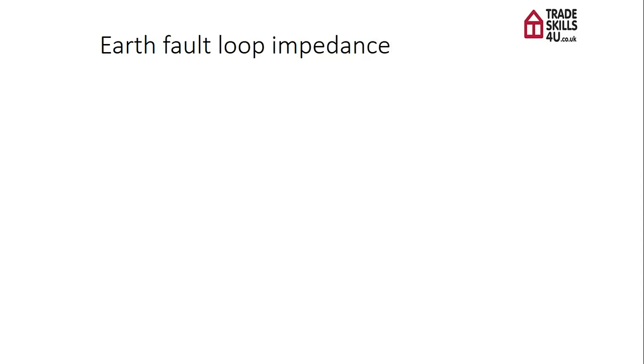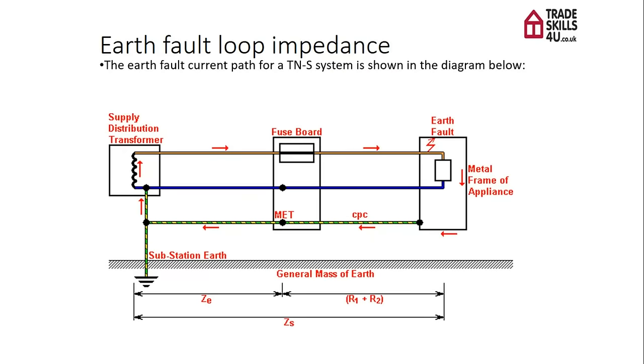The purpose of a ZE test is to determine whether or not an installation has a sufficient means of earthing. In this diagram here, I'm showing the earth fault current for a TNS system and the main earthing conductor, coming from the distributor and connecting to the main earthing terminal, or coming from an earth electrode or earth rod if this was a TT system. It has to be checked to make sure that it's continuous, that there's no break in it.